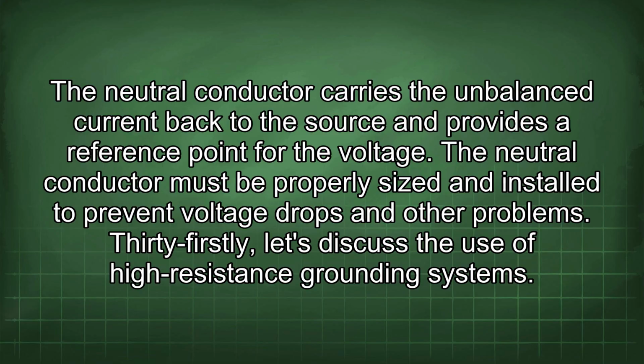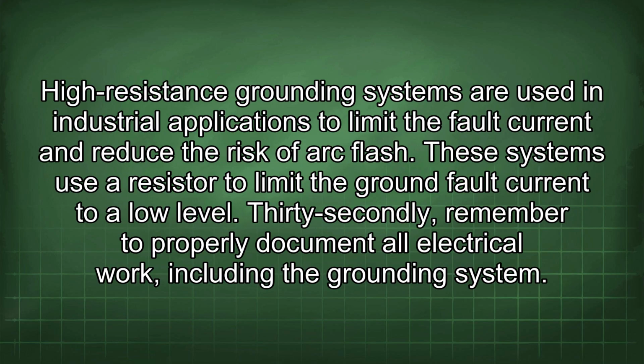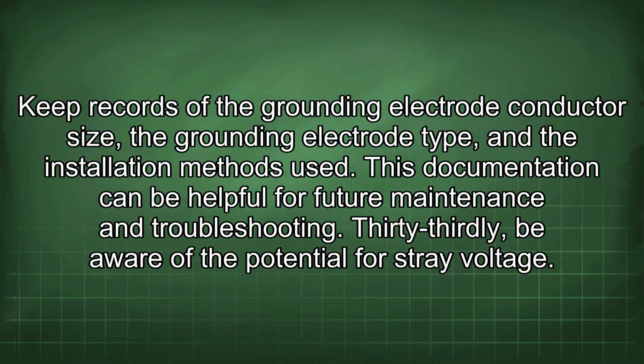31stly, let's discuss the use of high-resistance grounding systems. High-resistance grounding systems are used in industrial applications to limit fault current and reduce the risk of arc flash. These systems use a resistor to limit the ground fault current to a low level. 32ndly, remember to properly document all electrical work, including the grounding system. Keep records of the grounding electrode conductor size, the grounding electrode type, and the installation methods used. This documentation can be helpful for future maintenance and troubleshooting.